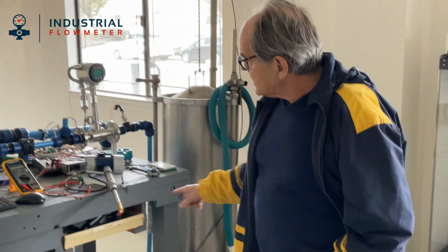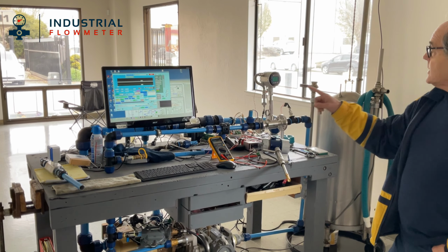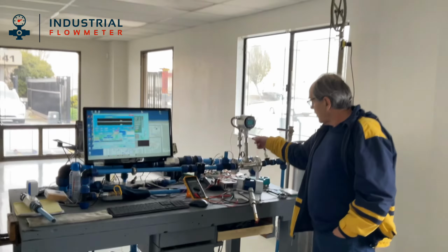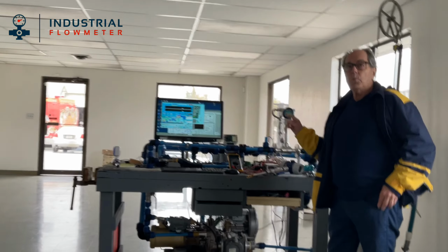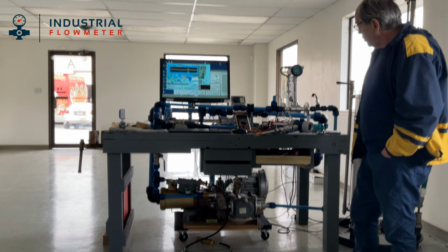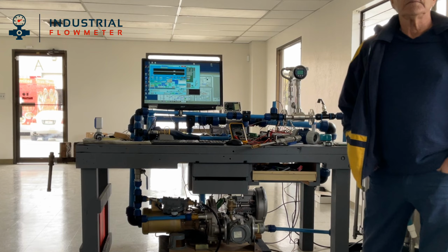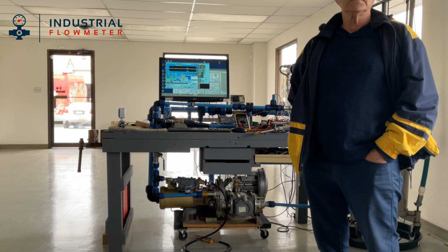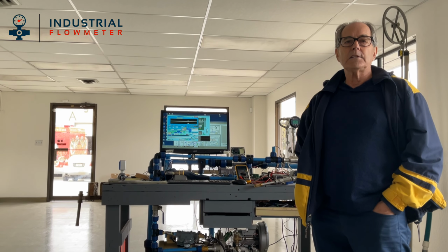But nonetheless, once it's closed and there's no leaks, it's flowing gas, that gas that you put into it, we now characterize this flow meter, or whatever flow meter, with that gas, with this closed loop system. So I just want to back up here, and this lets us know exactly how much flow is flowing through the system, and then we can use that to calibrate. Is that right? Is that accurate?